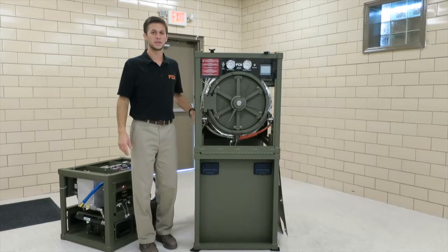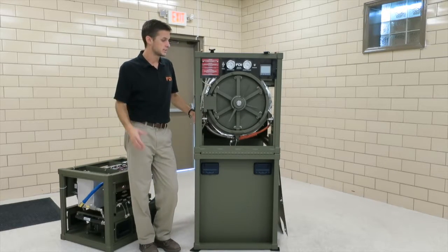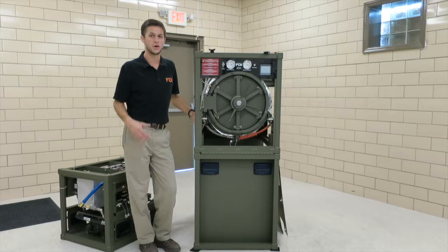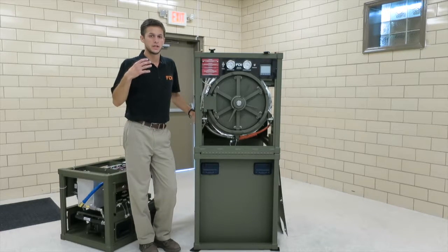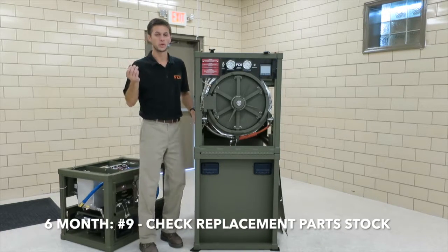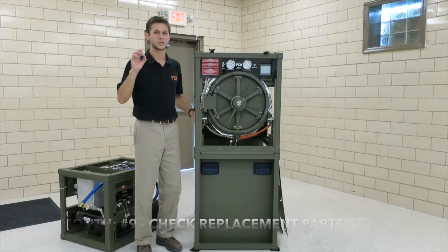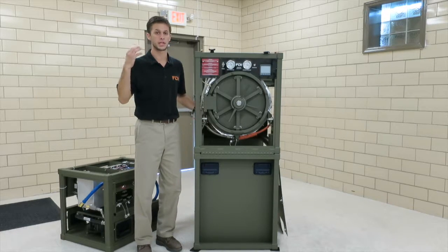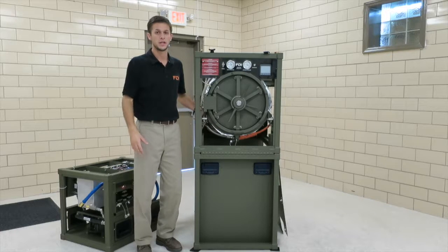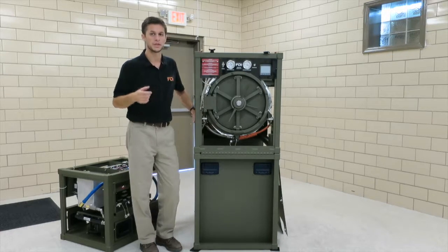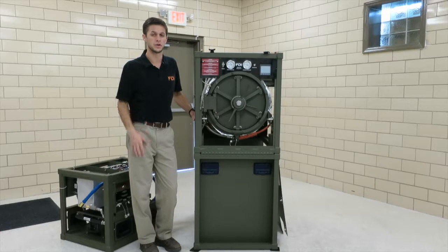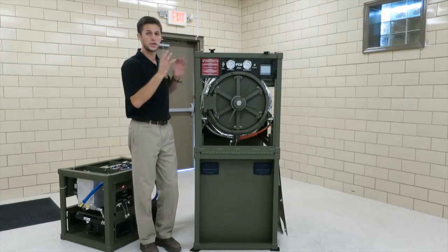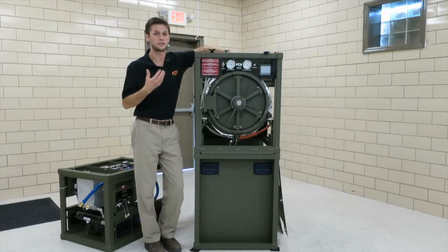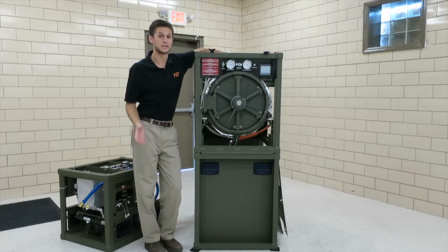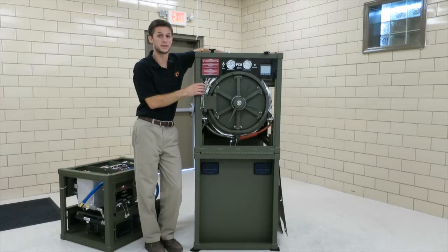Lastly, on the 6-month preventive maintenance list is to check and make sure that you have all the replacement parts available. Those parts are in section 4.4, and we have put an asterisk next to all the replacement parts that we recommend that you stock. So you don't have to do this, but it is recommended that you have those on hand. Those are what we've deemed the most likely to fail, and so if you have those on hand, you'll be able to do your maintenance much quicker and get back up and running.